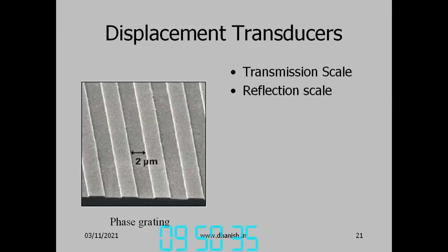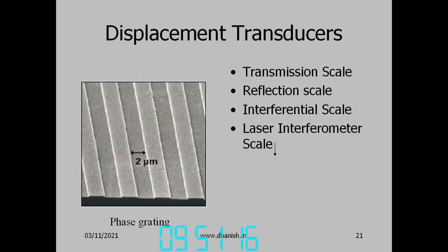Then we have the reflection scale. The only difference is that the scale is a metal scale, so we cannot view it through the scale, but the reflections are monitored. And then the interferential scale. Here we view the interference fringes generated by light coming out of two adjacent transparent portions. Between them there is interference, and we measure the movement of interference fringes. There is a lot of amplification possible, and thus it is much more sensitive. But of course it will be more costly also. If the source of light for the interferential scale is a laser instrument, then it is a laser interferometer scale. That is also possible.